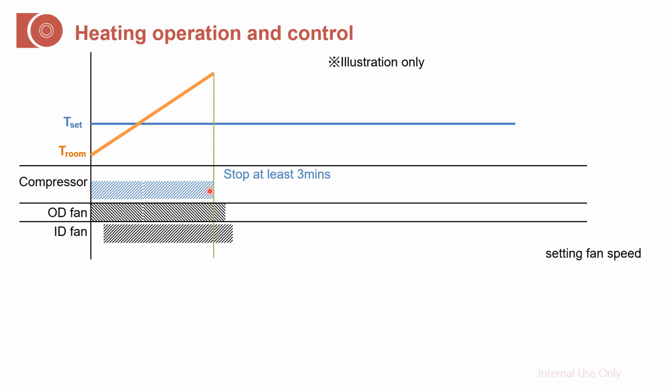And for the compressor, when it stops, it will stop for at least 3 minutes. During these 3 minutes, no matter what the room temperature is, even if it drops to a very, very low value, it will not start again. As for the outdoor fan, it will stop after 30 seconds. How about the indoor fan here? It will just blow out the residual heat.